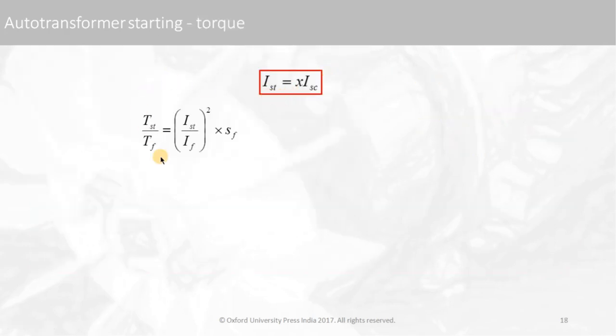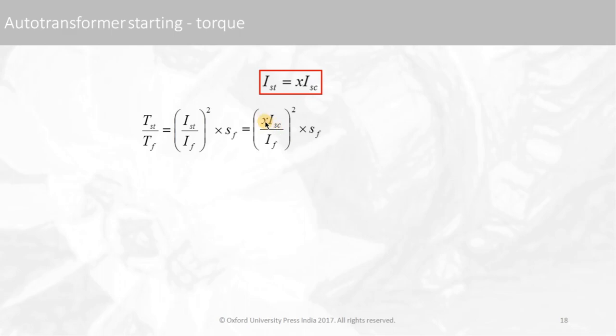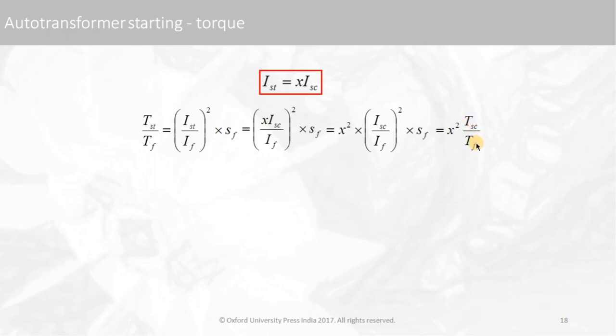For the torque: T_start / T_full-load equals (I_start / I_full-load)² × s_full-load. Substituting I_start = x · I_sc gives x² outside the bracket, and the remaining term (I_sc / I_full-load)² × s_full-load is nothing but T_sc / T_full-load — the short circuit torque ratio. After simplification, the full load torques cancel, giving the starting torque as x² · T_DOL_start.